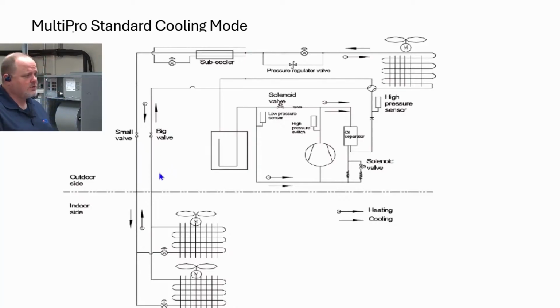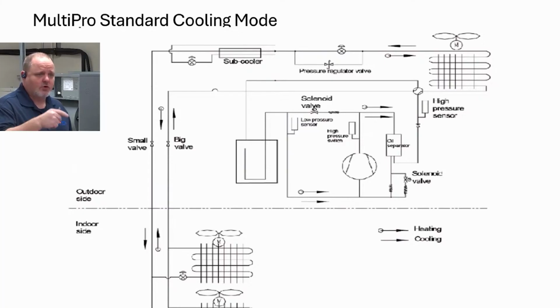So in a lot of piping diagrams that you will see in the MultiPRO mini split world of heat pump systems, they call them small pipe, big pipe, or they'll call them liquid and gas. Right, because it could actually be hot gas or it could be low pressure gas. And then if you venture off and go into commercial three-phase equipment, a lot of those are three pipe, where you've got a low pressure gas, a high pressure gas, and a liquid. Those are heat recovery, right? Yeah, in a heat recovery system. So that's why that terminology is used that way, so it's less confusing when you're talking equipment in that world of equipment.